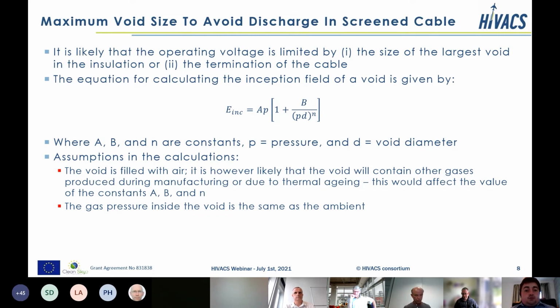I'd like to say that there are two very important assumptions that this analysis makes. The first is that the void is filled with air. However, there is a very fair chance that the gas inside the void may not be just pure air. So there are things like gases that may be trapped inside the void during manufacturing or evolved due to thermal aging that may change the values of these constants.